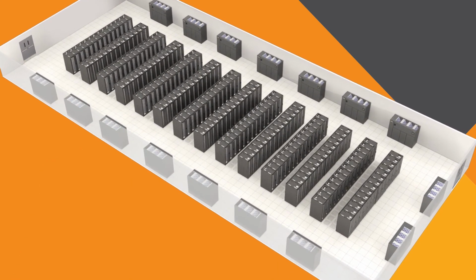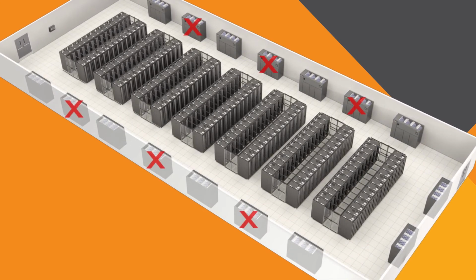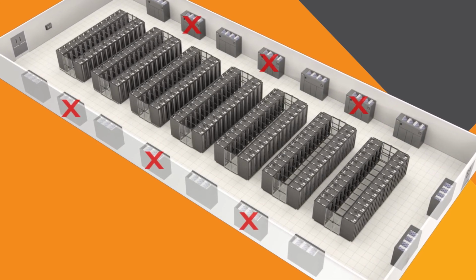And with variable speed fans, new controls, and containment, you'll be able to run at a higher return air temperature. So you'll go from having to run 16 units to just 10. That will let you put some of the units in standby for redundancy.